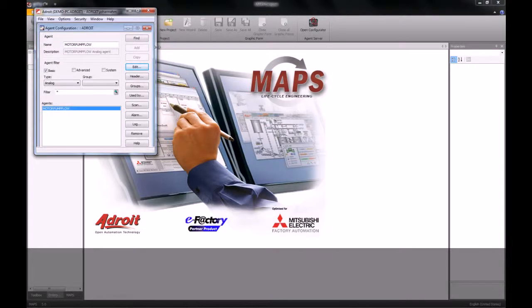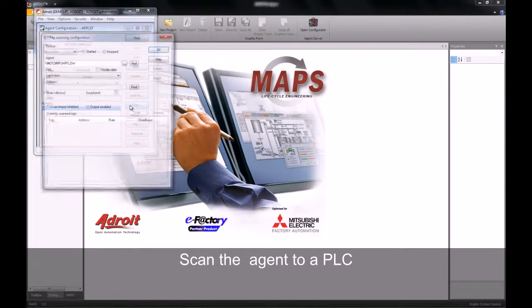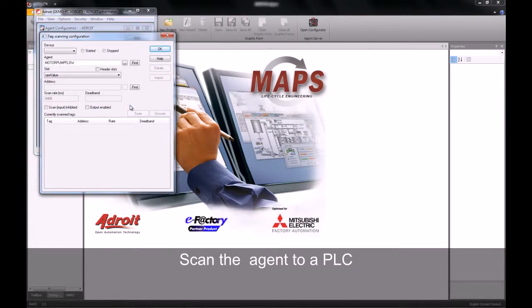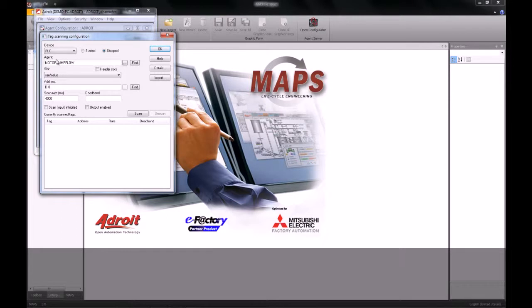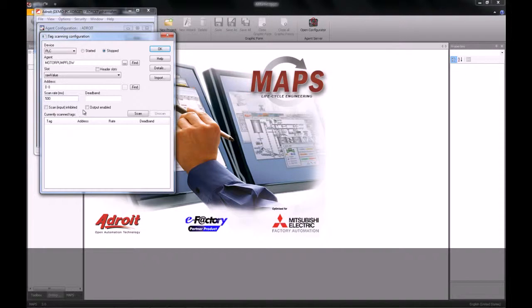We can now go and attach this to a PLC's registers. To do this, click on the scan button which will open up our scanning dialog. We then go along and select the device — in our case it will be the PLC device which we configured in a previous exercise. I'm going to leave my address as the default and change my scan rate to 500 milliseconds.